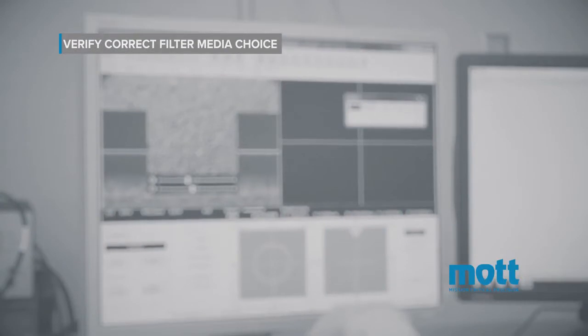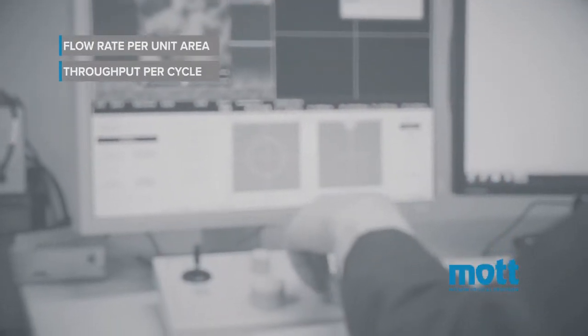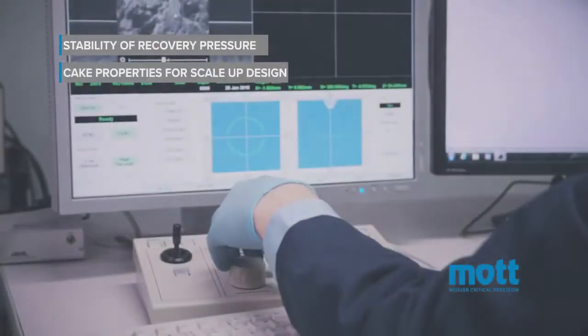The data gathered from disk feasibility testing is used to verify the correct filter media choice, flow rate per unit area, throughput per cycle, stability of recovery pressure after backwash, and cake properties for scale-up design.